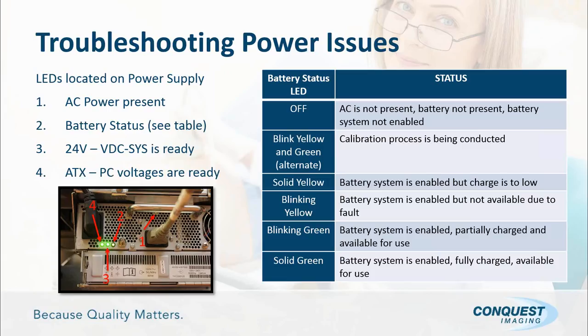Then we move on to the third light, which is your 24 volts DC is ready. The system power does not have to be on necessarily. This light can be on with a power in the off state. It's simply saying I do have 24 volts. It is in my range. I'm ready to go when you are.